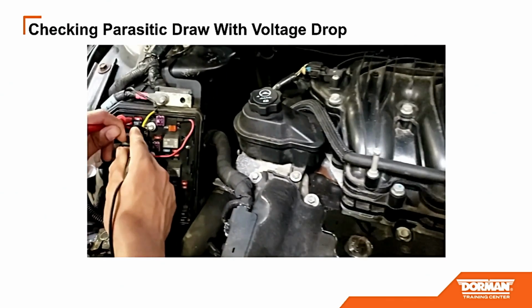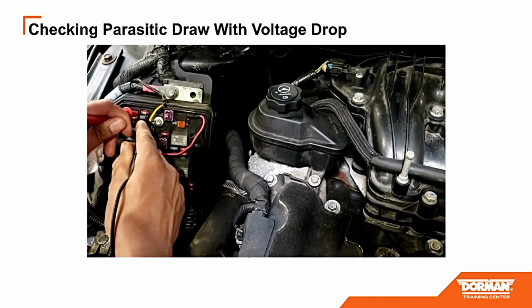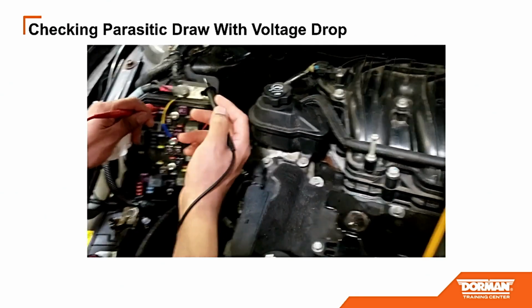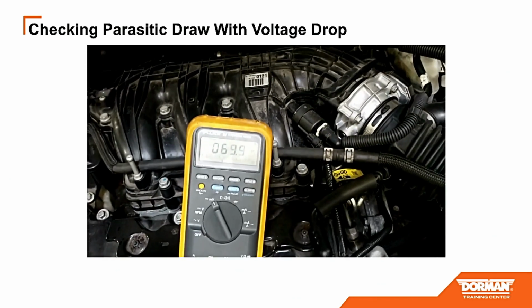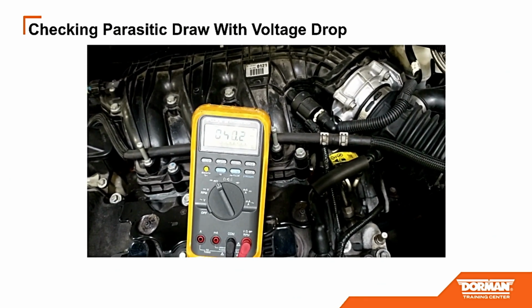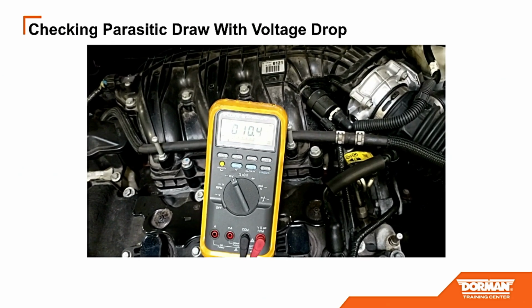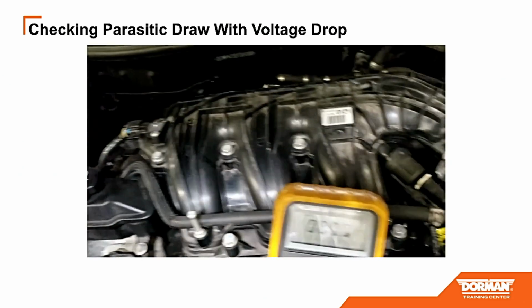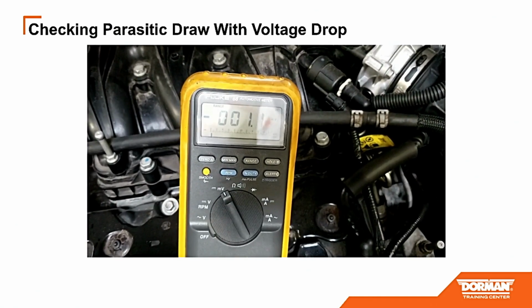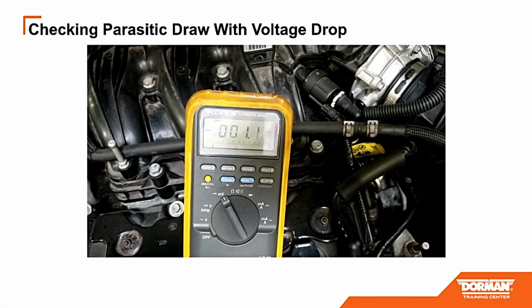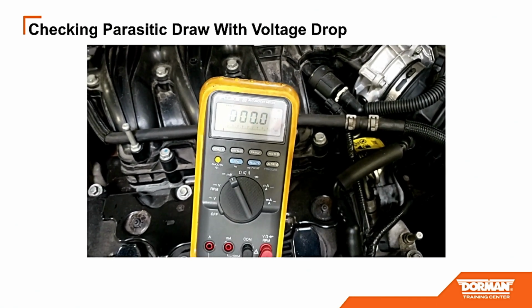Notice we're at 0. He's on a fuse, but go off the fuse for a minute and show us ghost voltage. If you got ghost voltage, you see it bouncing around - you're not connected. Go near the fuse but don't hit the metal part. If you're near the fuse and not on the pin, you're still going to be bouncing around. Now go on the pin - we'll get a solid 0.